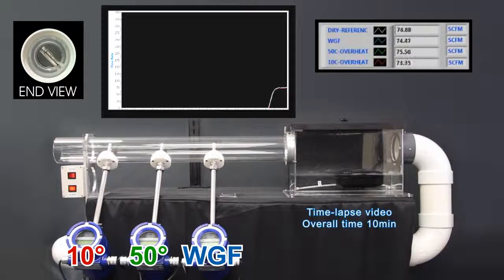The humidity just leaving the digester is at its highest condensation, which is where access is usually the easiest. Among the three flow meters, the WGF is placed closest to the wet source.